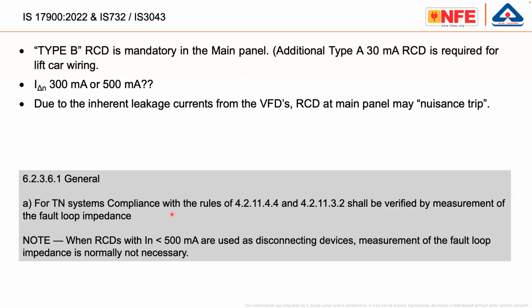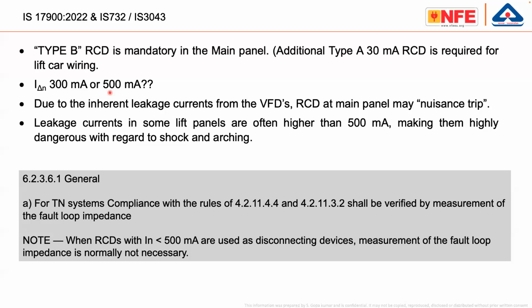So the subjects which we have to discuss are how we are going to achieve the fault protective measure, whether the RCD is mandatory or we can do it with an OCPD, MCB or fuse, and how we handle the cases of nuisance tripping due to the leakage current of the VFD. And one more subject which we always neglect is, in the case of a TT system, whenever there is a fault on the HT side of the transformer, the LT side electrical appliances are stressed. As a result, they may fail.